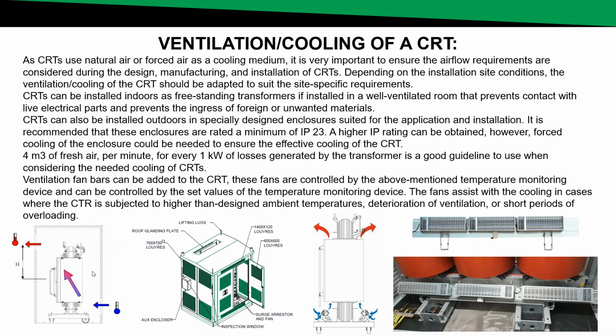So if you look at the picture, it's clear that cast resin transformers use natural air cooling. So cold air comes through the bottom, it heats while it's flowing through the transformer, and hot air leaves out the top. So taking that into consideration, as mentioned, you need to ensure that the area the transformer is installed in is suitable for the cooling needed for the transformer.